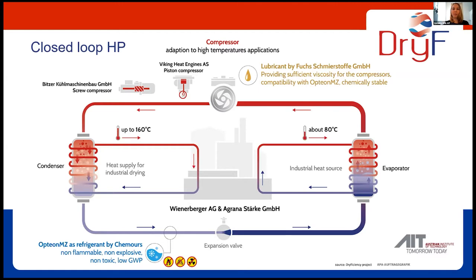The scientific name is R1336MZZ(Z). It has been developed for high temperature application, and it's a low GWP refrigerant. To create a stable system with the lubricant at high temperatures, our partner Fuchs spent a lot of development work in the project, and that solution is now tested in the demonstrators. After the compression, the refrigerant has high temperature and pressure, and it's condensed in the condenser to deliver the heat for the industrial drying processes. Here we aim to reach 160 degrees C, and you will hear more about that in the presentations by our demonstrators.